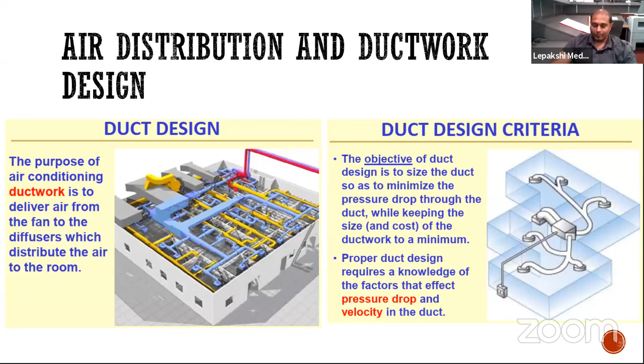And it's got to be properly designed. It can't be too huge, big ducts. You can't put them over there. The first impact is that it's going to take a lot of space. Second, it's very costly too. So keep in mind, while designing a duct system, you have to minimize the pressure drop throughout the ductwork system, keeping the size of the ductwork to a minimum. These are the duct design criteria. You have to consider space, installation costs, air friction, noise levels, duct heat transfer, and so on.